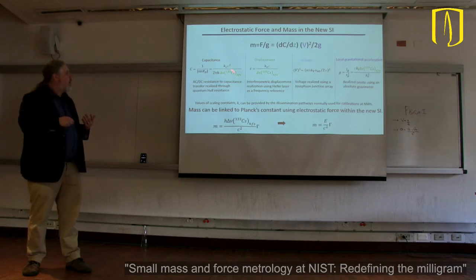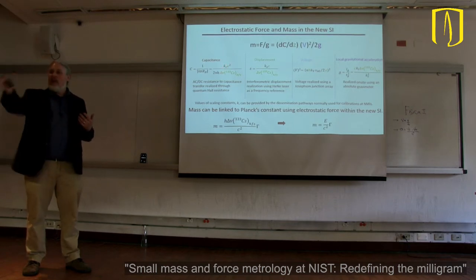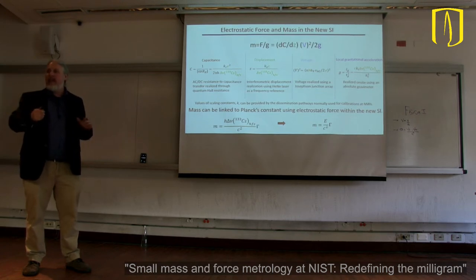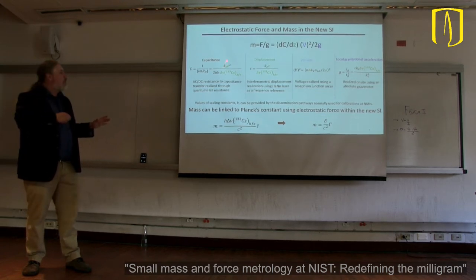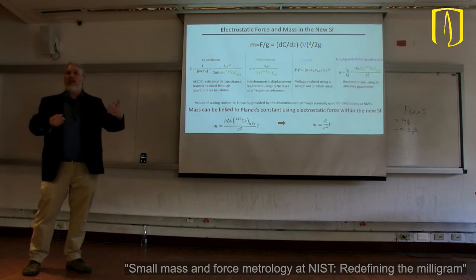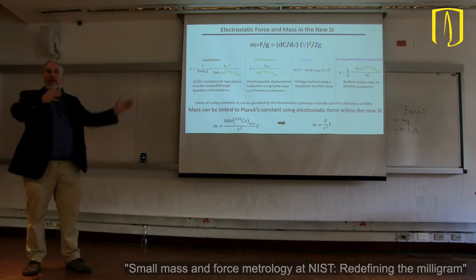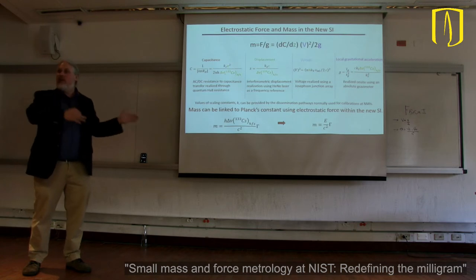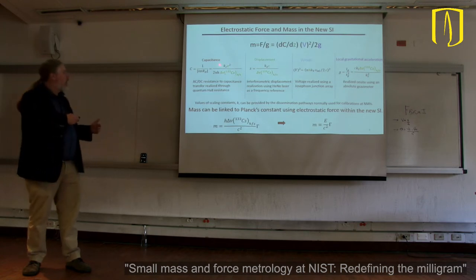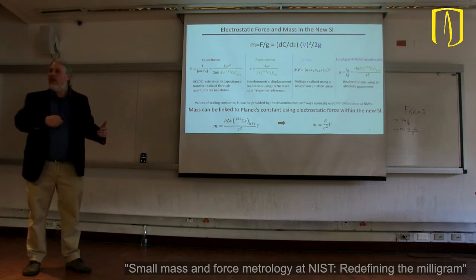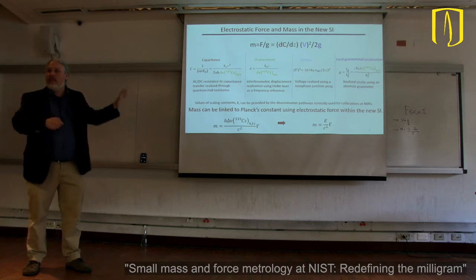Right? And so we can measure capacitance using a chain of calibrations. That's that K here. This is John Escobar, who works at INM here in Colombia. They take these fundamental standards, and through their calibration processes, put them in a box that you can use in your laboratory. And that is this KC here.